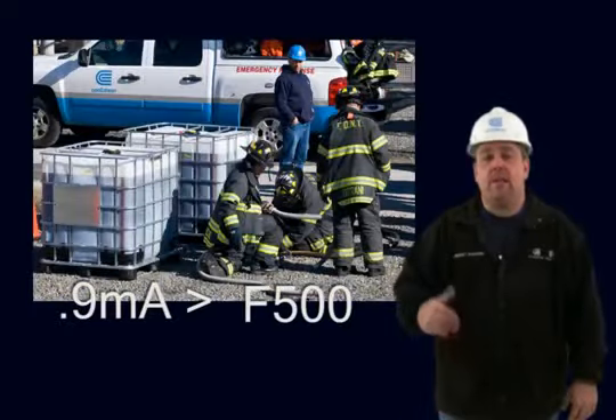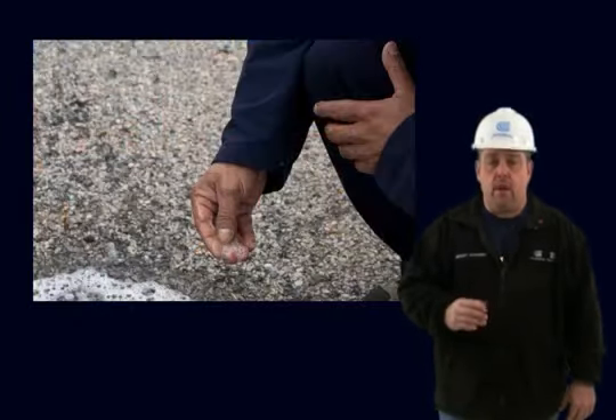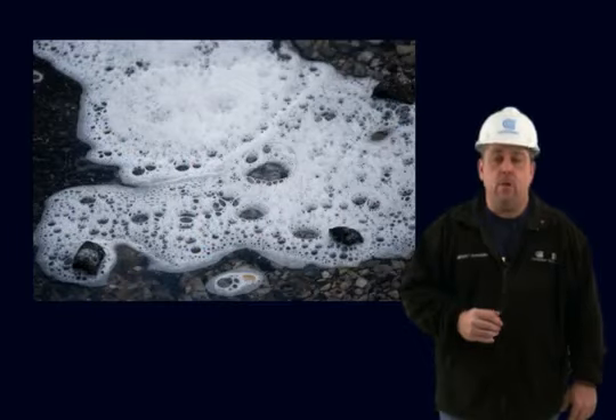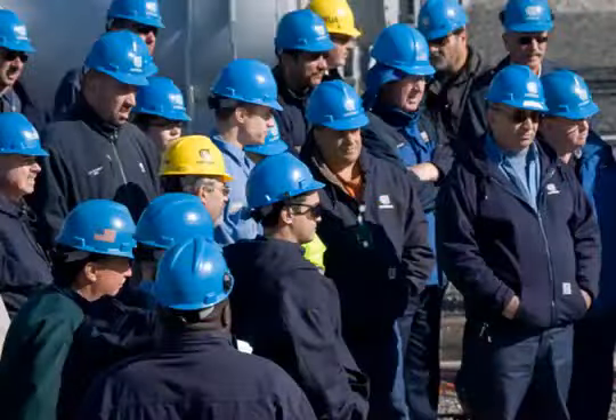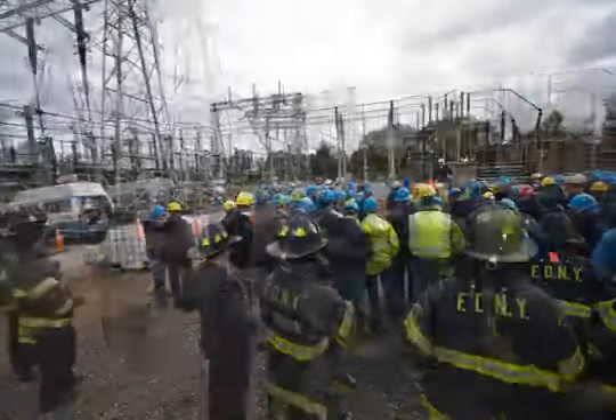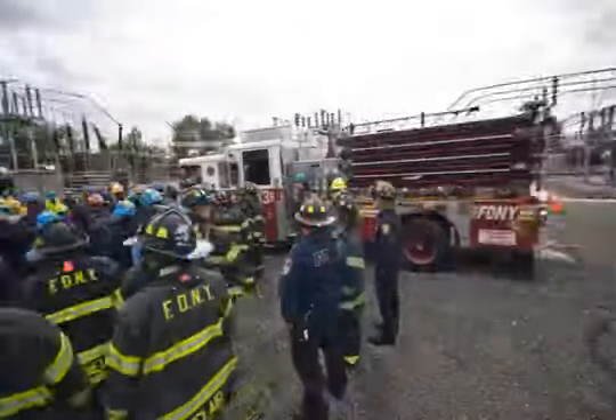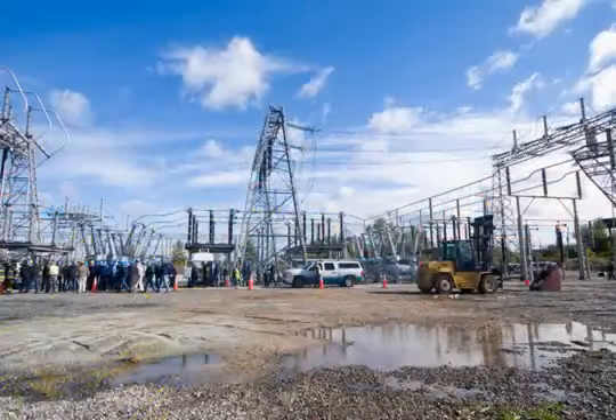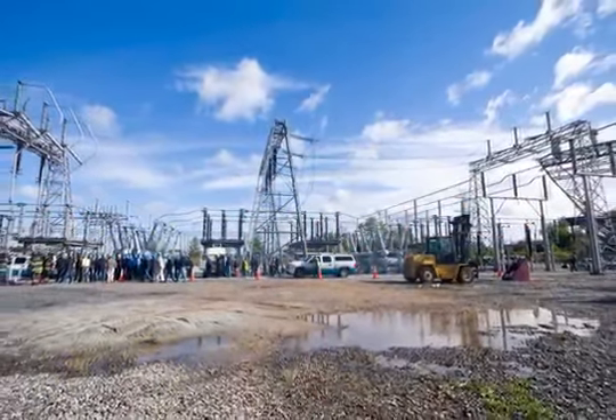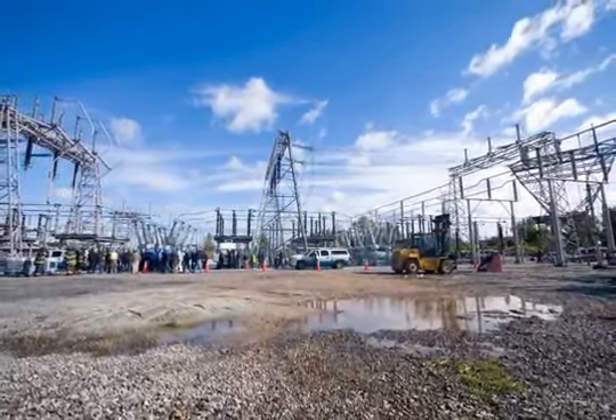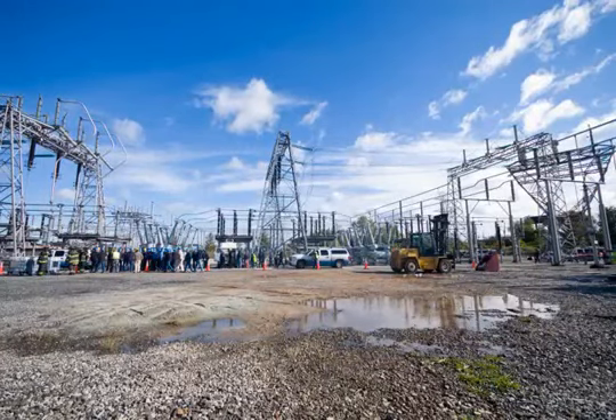F500 does not fall into the category of traditional foam. It is considered an encapsulating agent capable of providing quick knockdown coupled with heat dissipation. These promising test results enabled us to move forward and conduct a live field test at the Fresh Kills substation. The selection of this site was driven by our need to conduct the testing on the highest voltage that the fire department could reasonably encounter.